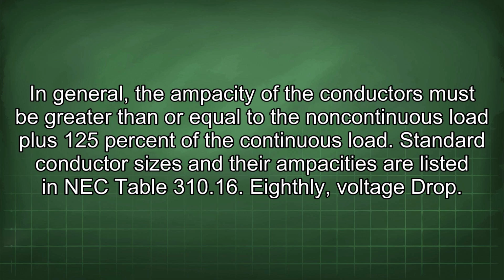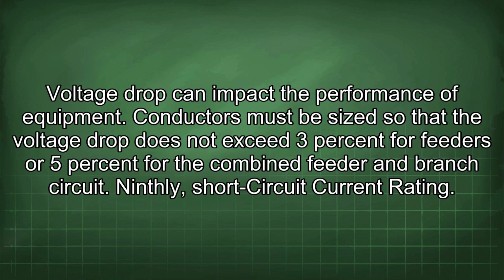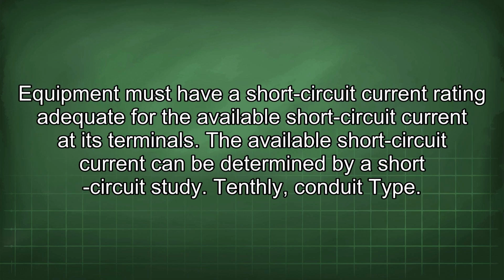Eighthly, voltage drop. Voltage drop can impact the performance of equipment. Conductors must be sized so that the voltage drop does not exceed 3% for feeders or 5% for the combined feeder and branch circuit. Ninthly, short circuit current rating. Equipment must have a short circuit current rating adequate for the available short circuit current at its terminals. The available short circuit current can be determined by a short circuit study.